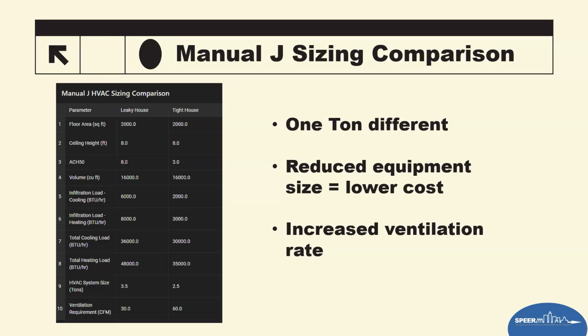The tighter the home, the more mechanical ventilation that we need, and the more it needs to be verified that it's happening so that the occupants do not have any undue stress over contamination or a buildup of VOCs or pollutants inside the house. So of course, being 1 ton oversized, that now is going to be what's called short cycling. So this is going to allow humidity to start to rise during those humid times of the year, especially during the shoulder seasons where those systems don't run long enough.